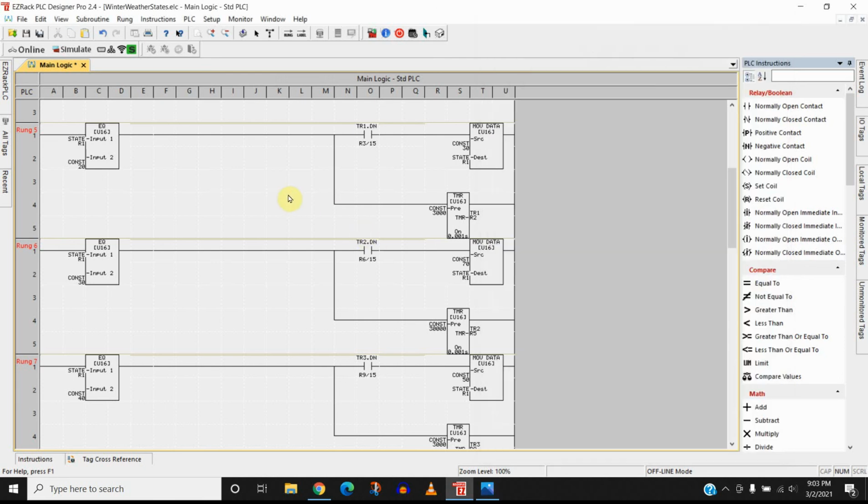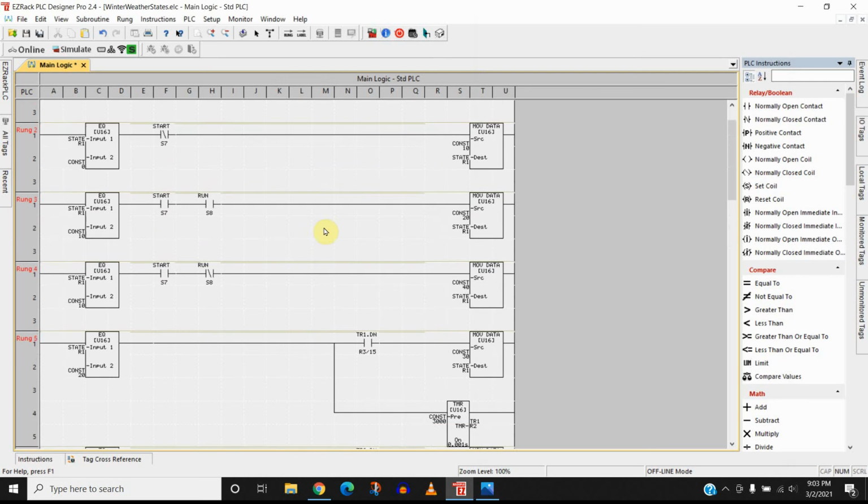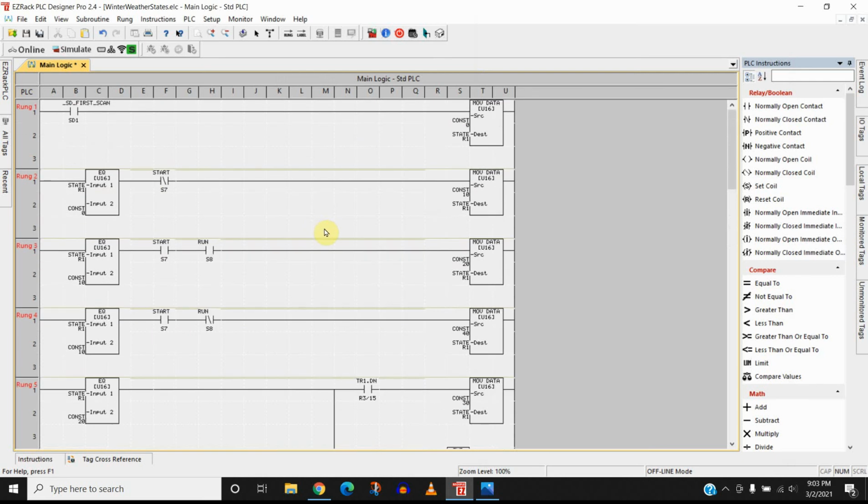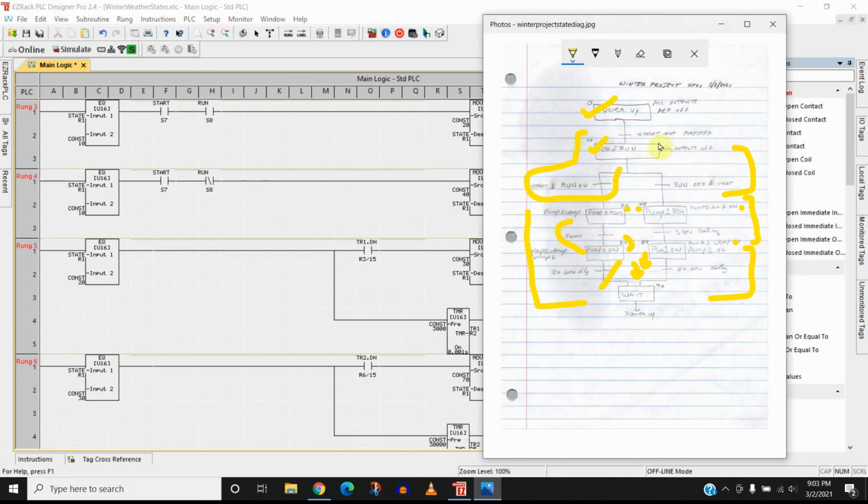So anyway, to summarize, this is a very simple way to tackle complex problems that have all sorts of cycles and restart points and restart conditions and fault conditions. Anything you can think of, we can put it in here. If you wanted this thing to fault, if you had start pressed when it powered up, we would jump out to state 100, and that would be a fault condition, and I could flash both of the pump indicator lamps at a high rate of speed. Whatever I want to do, I can easily add that to it.